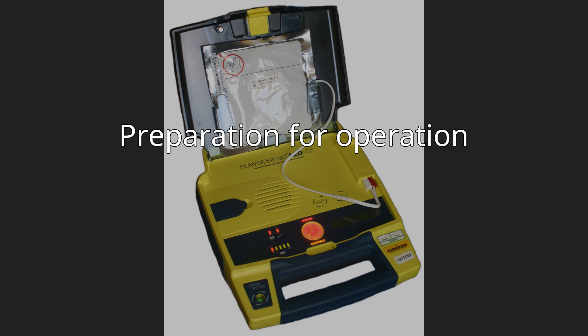It is also important to ensure that the AED unit's batteries have not expired. The AED manufacturer will specify how often the batteries should be replaced. Each AED has a different recommended maintenance schedule outlined in the user manual. Common checkpoints on every checklist include a monthly check of the battery power by checking the green indicator light when powered on, cleanliness of all cables and the unit, and checking for adequate supplies.